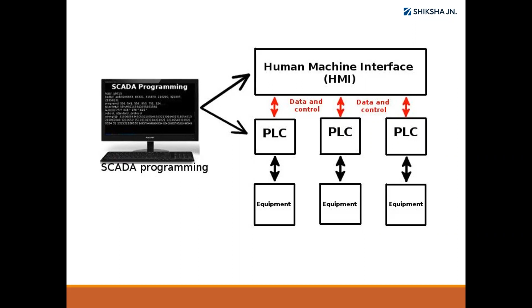SCADA programming, or SCADA generally, connects like this. You can see here, SCADA can be connected to multiple PLCs. It can also be connected to an HMI system. HMI is basically for a particular one machine or one piece of equipment, whereas SCADA is for the entire process, the entire plant. Again, PLC is connected to individual equipment, just like one or two conveyor systems, it will be connected to PLCs. So PLC can be connected to multiple equipment, but for remote operation, PLC is not suitable. For that you have to use SCADA. So SCADA can be connected to multiple elements through PLCs.